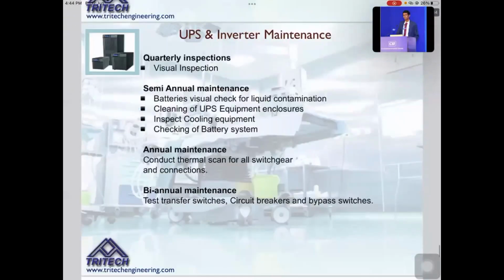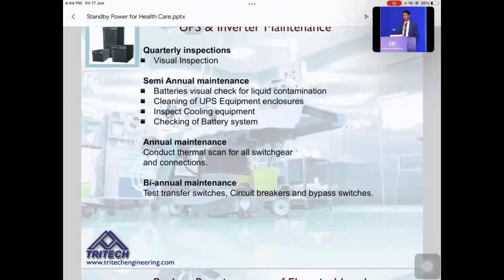Similarly, for the UPS, we need to maintain various periodic inspections: quarterly, semi-annual, annual, biannual, and so on. The batteries need to be checked visually. The UPS equipment, the enclosure, as well as the terminals need to be cleaned. For the cooling system, especially in a closed area, you need proper HVAC and AC units working properly, and of course the battery system. And similarly, you need annual and biannual maintenance. All these are listed here.